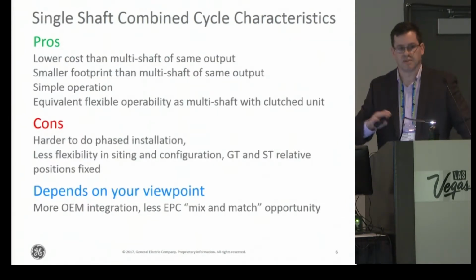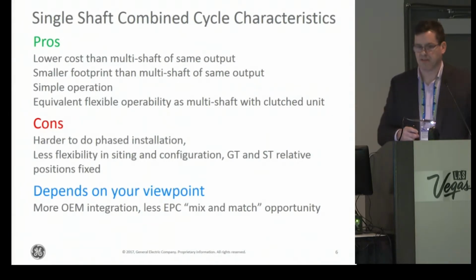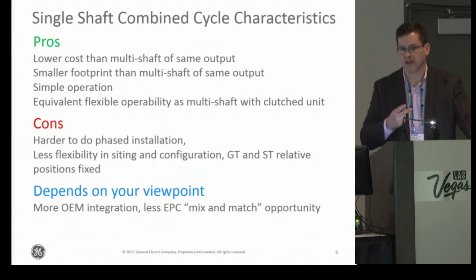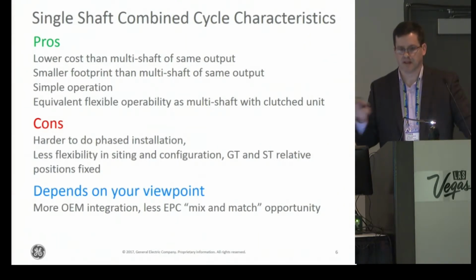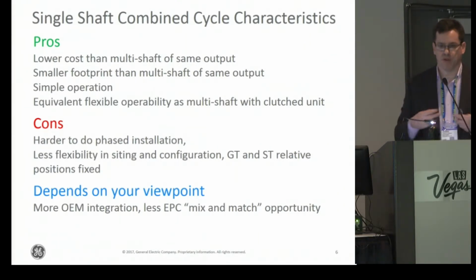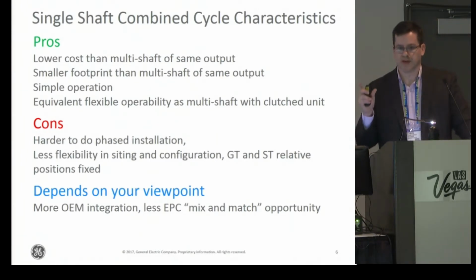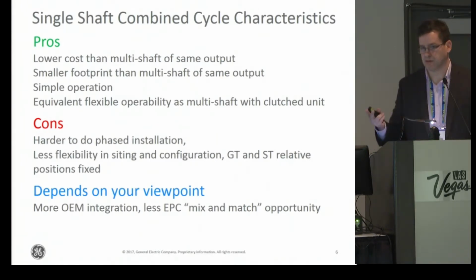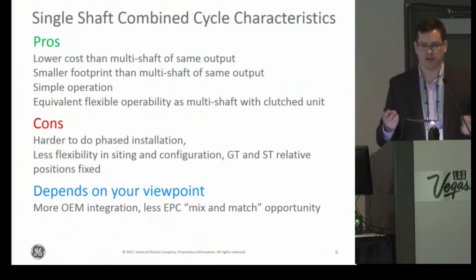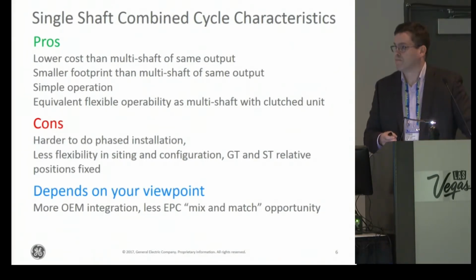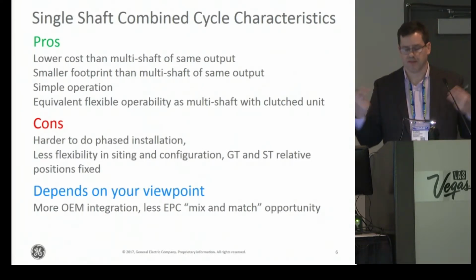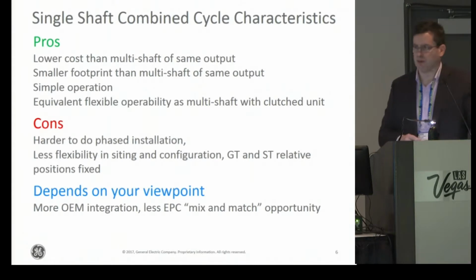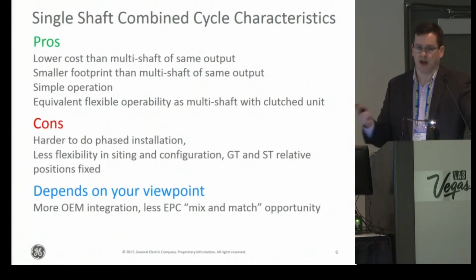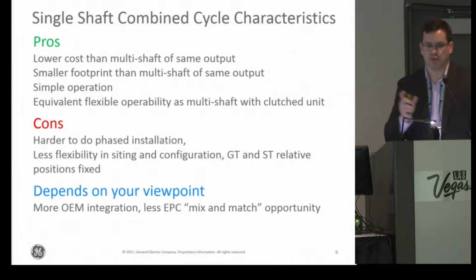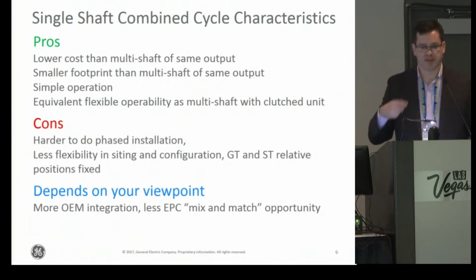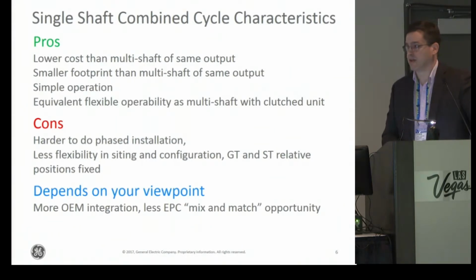Now, you already heard some of the pros and cons of single shaft versus multi-shaft. If you look at a one-unit gas turbine site, the single shaft is typically going to be a little cheaper than the one-by-one multi-shaft. One of the reasons we see for that is the one larger generator being less expensive than two smaller generators, one set of electrical hardware instead of two. Also, you have a much more compact footprint. Everything's connected together, smaller, easier to deal with, and you have the same flexibility of a multi-shaft plant as long as you have a clutch between that generator and the steam turbine, so that the steam turbine and the gas turbine can operate independently.